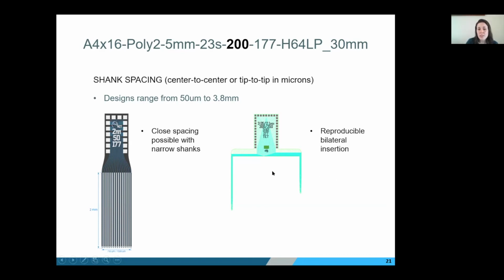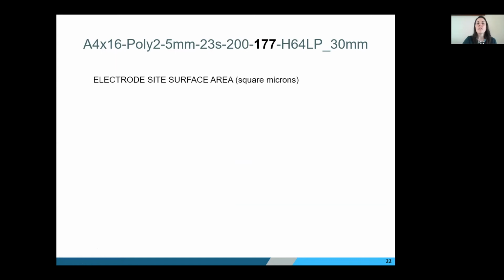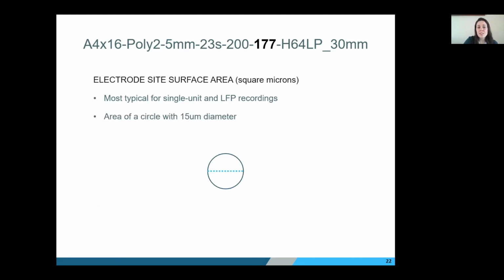So know that this is probably one of the larger ranges that we would go to, but anything in between, again, is an option. Now we're near the end. The next number is the electrode site surface area. So the units of this are square microns. And I know 177 sounds like a pretty random number, but this is actually our most typical site area. It's good for single unit recordings, also good for LFP recordings. And what it actually is, is a circle with a diameter of 15 microns. So I mentioned that before, but that's a nice round number. If you see the 703 surface area in our catalog, that's just a circle with a 30 micron diameter.